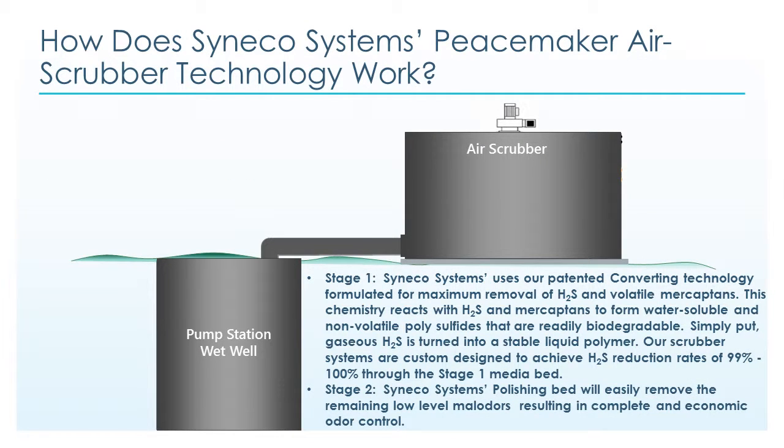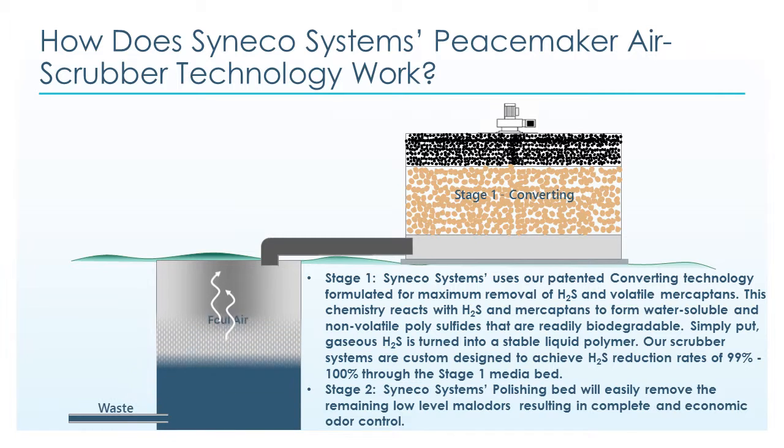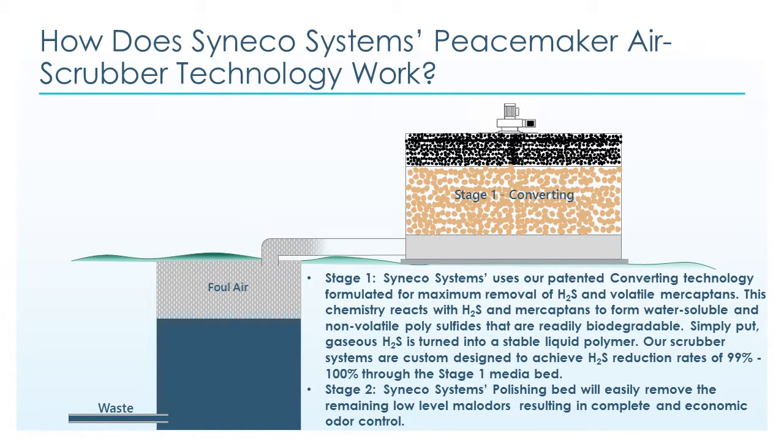How does the Syneco Systems Peacemaker air scrubber technology work? Our Peacemaker odor control with converting technology pulls H2S and other malodors from the pump station wet well or wastewater treatment plant application and pulls the gas through our two-stage media process. In stage one, with our converting media technology — unlike activated carbon that absorbs H2S — our patented converting media technology reacts with H2S to form a water-soluble and non-volatile polysulfide that is readily biodegradable. In simple terms, gaseous H2S is turned into a stable liquid polymer.